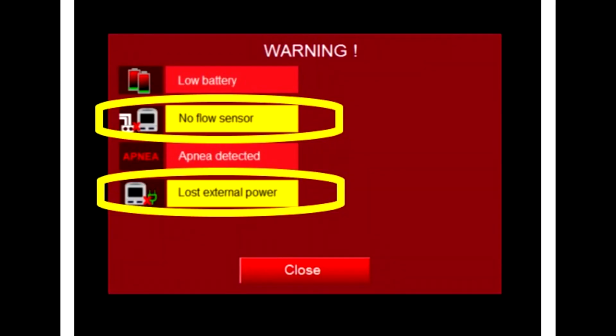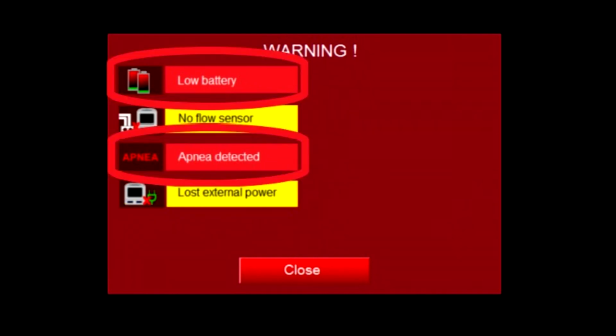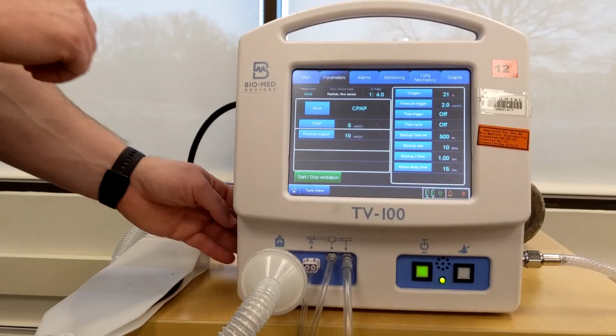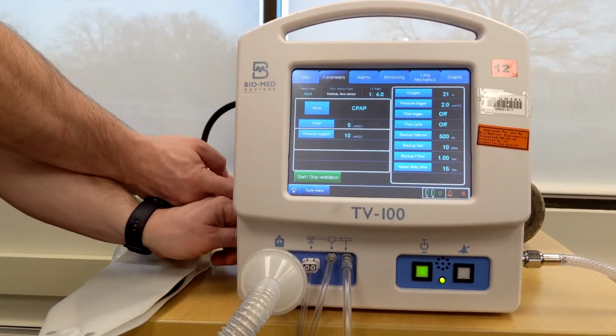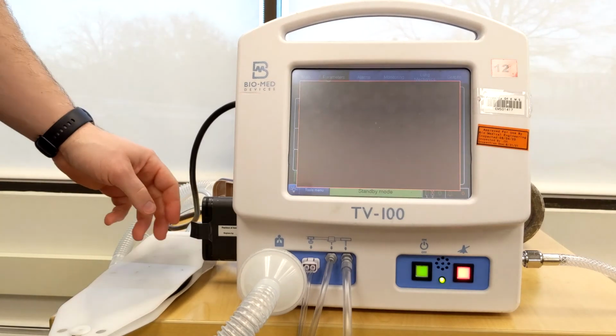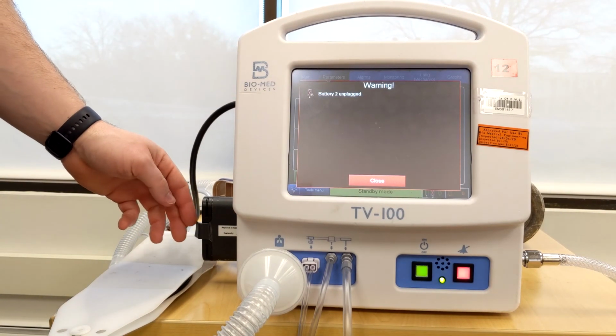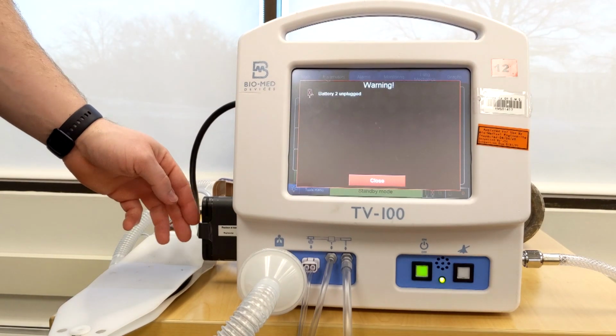The alarms can be broken down into 2 types, medium and high priority alarms. High priority alarm conditions occur when a mechanical, electrical, or software failure may render the TV-100 inoperable. High priority alarms are indicated by flashing the alarm button red at a frequency of 2.0 Hz and will make this noise.